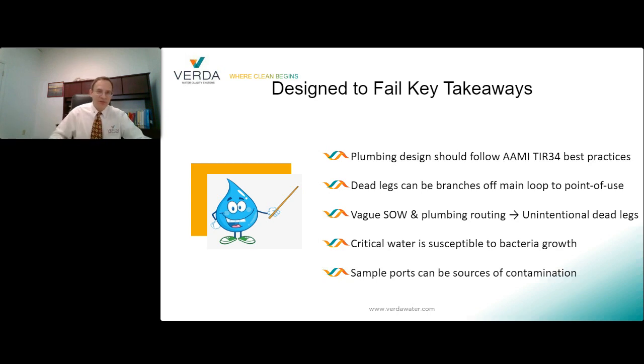At my company, what we do is we get the system up and running, we test for bacteria. Great, we get the results back, we test the second week. Boom, we prove we got 2 weeks in a row, no bacteria. We test a third week. We've now proved we got 3 weeks in a row, no bacteria. We test a fourth week. Got 4 weeks of data, now I disinfect. So now what have I done? I proved that I can go 30 days without bacteria growth, and then I'm disinfecting on a regular basis, on a monthly basis. I now have data to prove that once a month is adequate for my department, for my system.